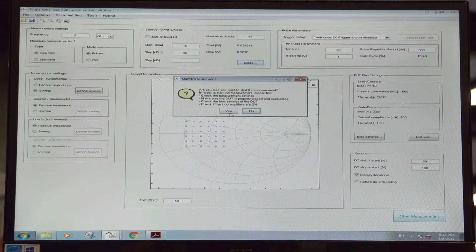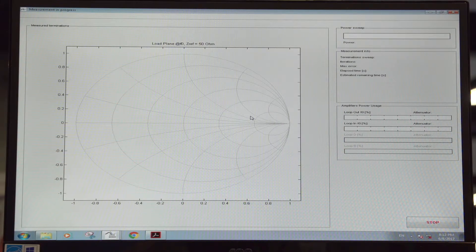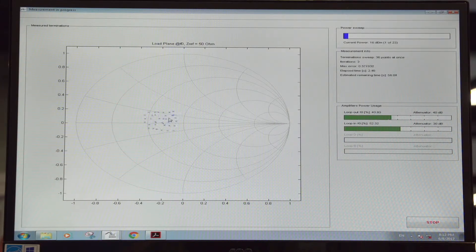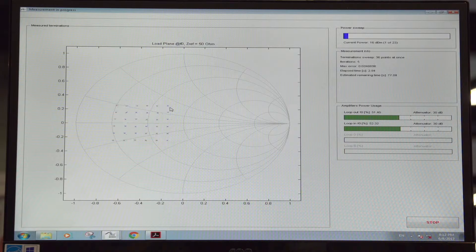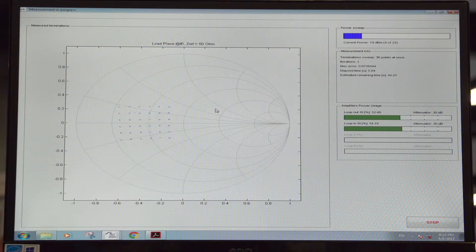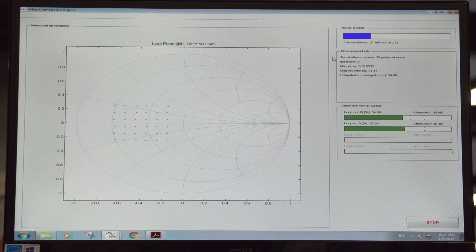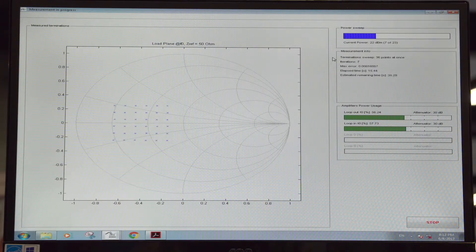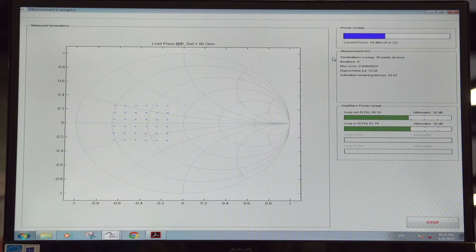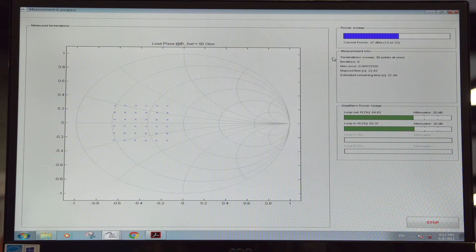So if I start a measurement, you'll actually see how quick the setup can measure. What you see here are the measured impedances that are provided real time to the transistor. And at each power level, the loads are provided and then the system sets up in power so that a full power sweep and load pull sweep is taken within a matter of about 30 to 40 seconds.